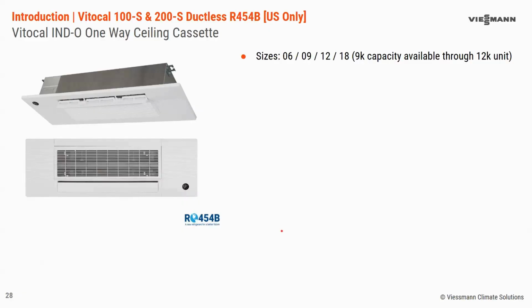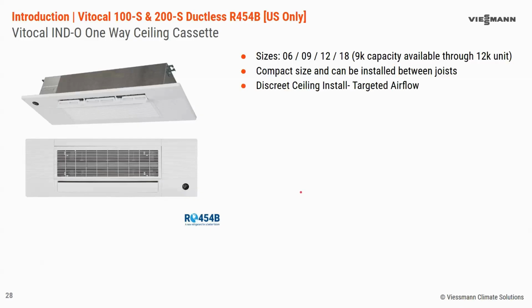Right. Similar to the four-way is the one-way. So this is available from 6,000 to 18,000 BTU with the 9K through the 12K unit being set in a dip switch. This has compact dimensions and is designed to be installed between joists. Again, another one that is within the ceiling. So the installation, that grill panel will be flush with the ceiling, but it allows you to have more targeted airflow than the four-way. For example, this can be installed in hallways or corners where a four-way would potentially have issues because of the four-way direction.